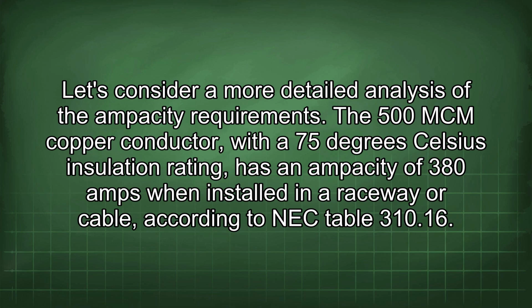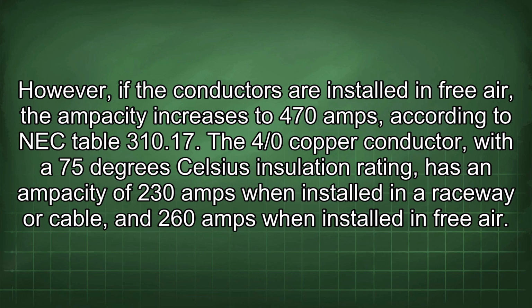The 500 MCM copper conductor, with a 75 degrees Celsius insulation rating, has an ampacity of 380 amps when installed in a raceway or cable, according to NEC Table 310.16. However, if the conductors are installed in free air, the ampacity increases to 470 amps, according to NEC Table 310.17.